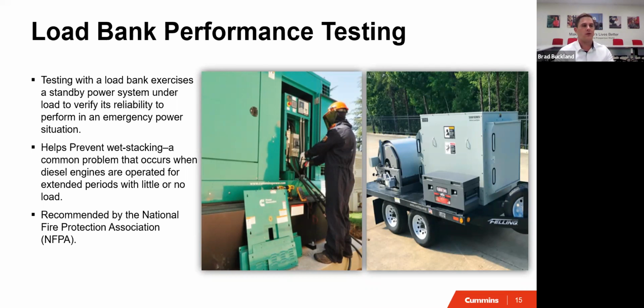And this right here, you basically just hook it up to the load bank. It helps prevent some wet stacking, which is when your generator doesn't operate at full capacity all the time. Some models of generator, it's just kind of a residue that starts coming out of the tops of the pistons of the generator or on the engine, and it can cause some damage. So it helps put your generator to the test and simulate it like power's been out once a year. That's always good to have to make sure there's no issues.